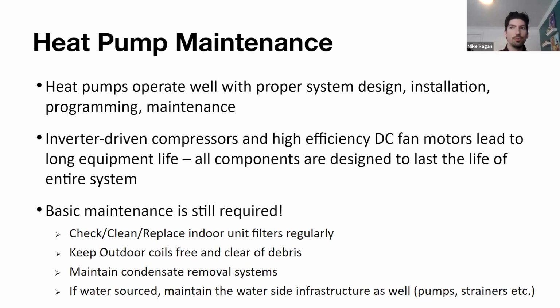leak. If everything was designed correctly, if it was installed correctly, and we nitrogen purged in all of our brazed joints, and we don't need to worry about corrosion, well, that's going to mitigate the need for maintenance down the line. But with that said, there is maintenance associated with heat pump systems. I certainly don't want to forget about that.